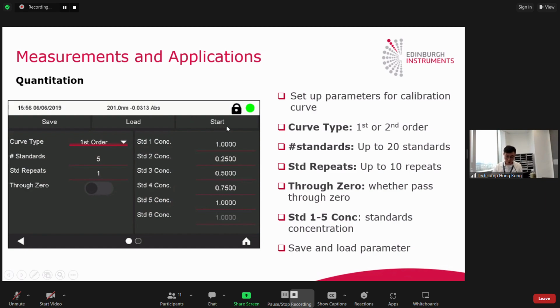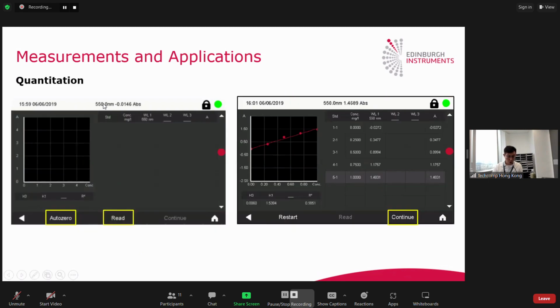Then you press the start button, and this screen will be displayed to measure the calibration curve. Remember to press the auto zero to do the baseline, and then press the read button. Then it will measure the points for the calibration curve. Here is the 5-point calibration curve shown in the example, and the calibration curve will be recorded in these pages.